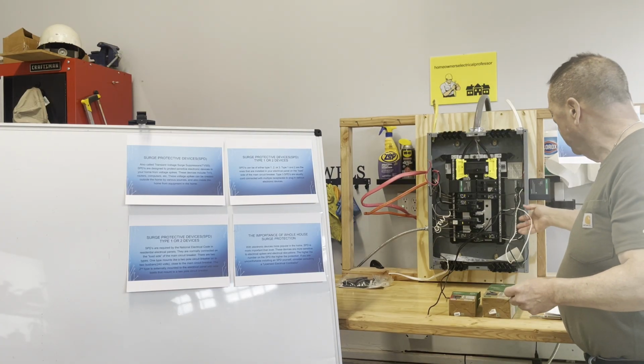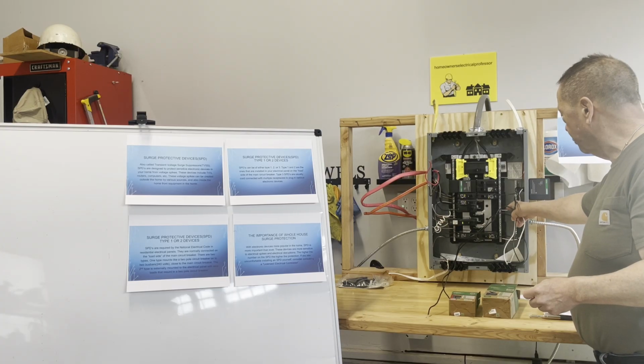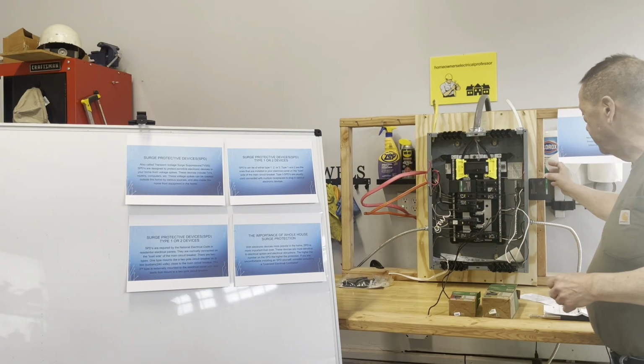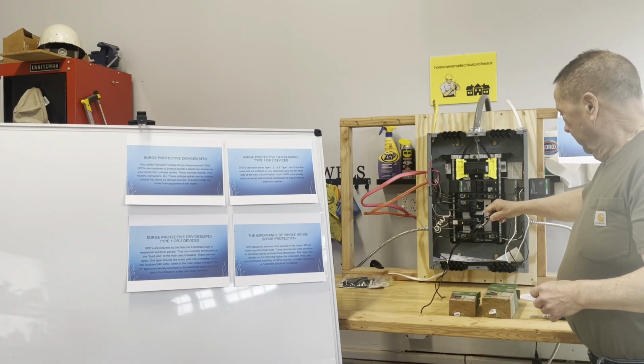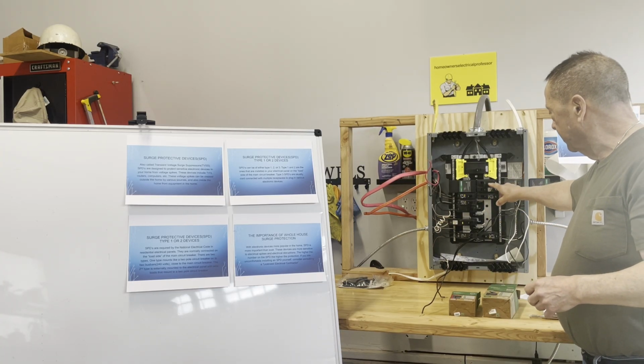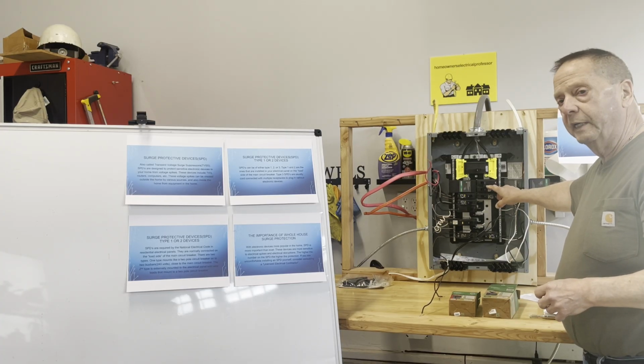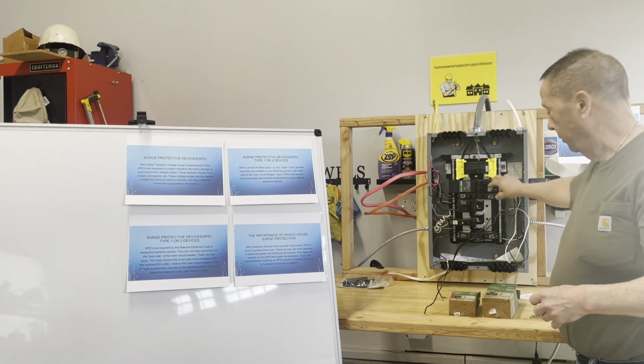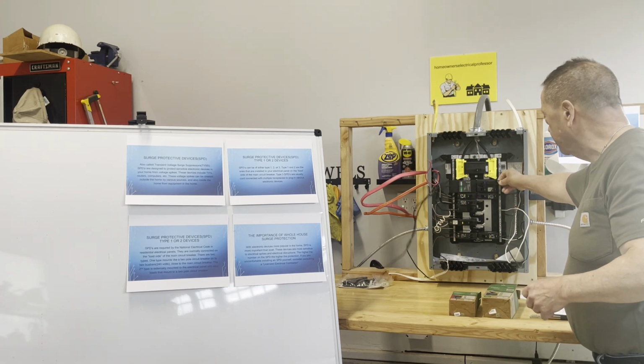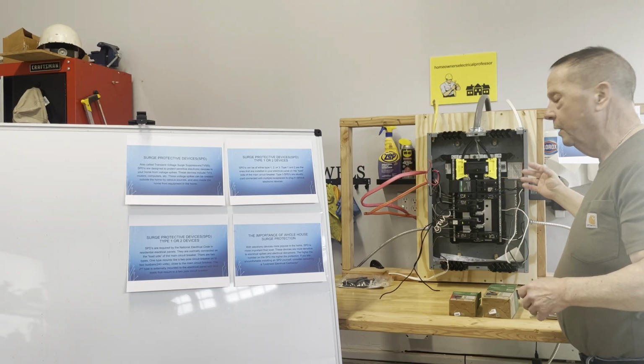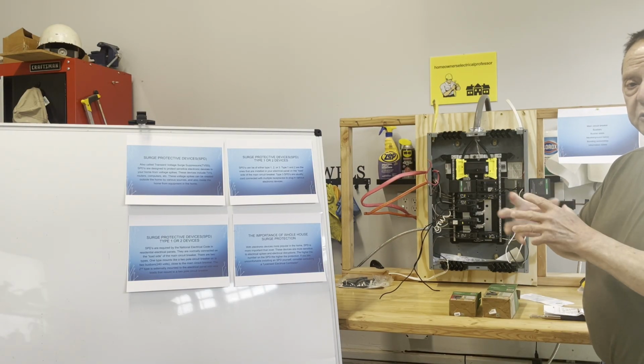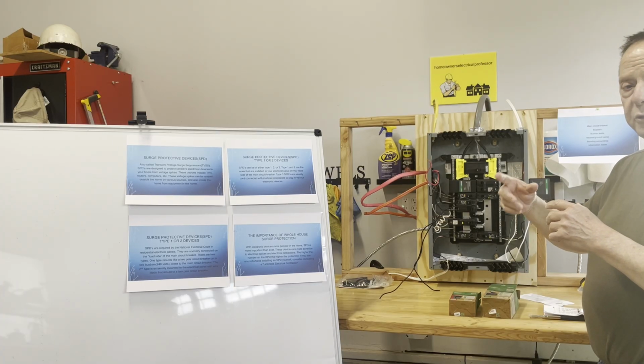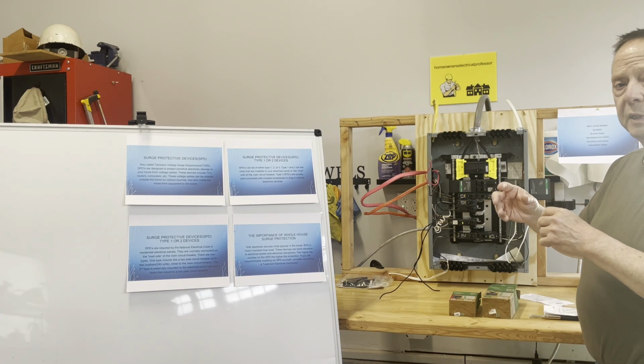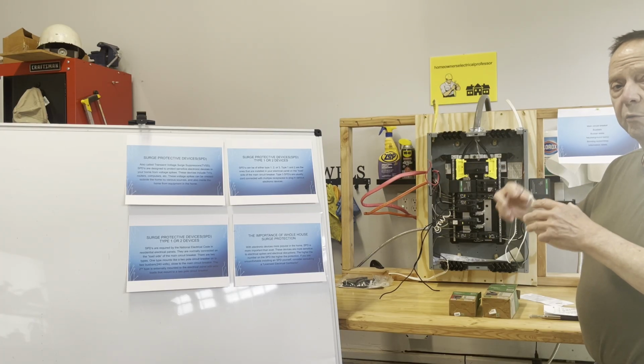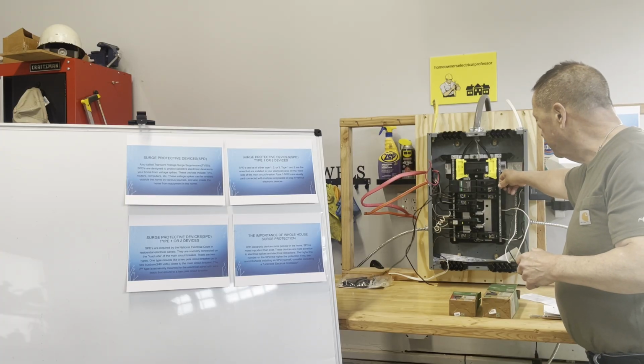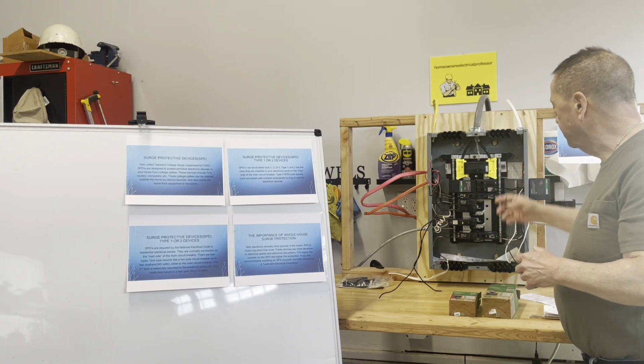Now with this type here, you would trim your wires down so they're as short as possible, because that's what the manufacturer wants. This particular one is a Square D panel, and they say you can put in either a 15, 20, or 30 amp 2-pole circuit breaker. Then you take these wires and trim them as short as possible, making them as straight as possible so there's no interference. When electrical wires are curled in an AC system, it can create magnetism, which could create interference, so you would trim these wires down so they fit as close as you can.